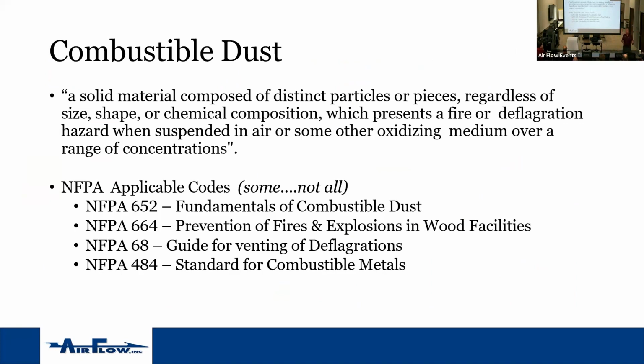So what we'll do with that is we'll drop another training session to go through just the changes that occurred in NFPA 660. Because NFPA in itself is exactly what governs a lot of what we do. In most cases, the NFPA is not necessarily a code or a requirement that you have to follow, but the authority that has jurisdiction on that site, that building, the AHJ, more often than not, could be your insurance agent, trying to protect and mitigate their exposure to any kind of issues. Could be the safety director at the place, could be a code official, could be a fire marshal. Whatever it is, they will follow and make you adhere to the NFPA standards when you go through it. So more to come on NFPA.